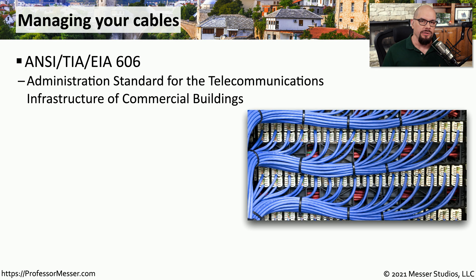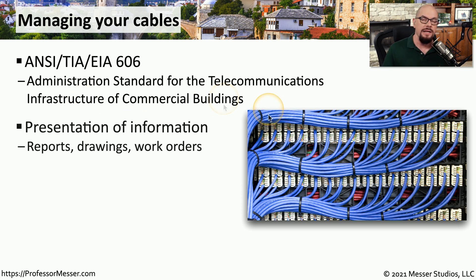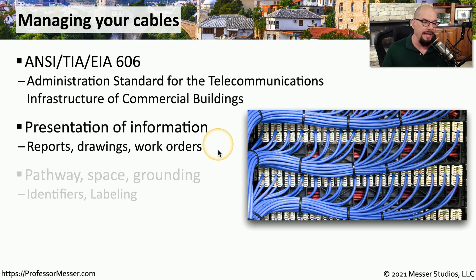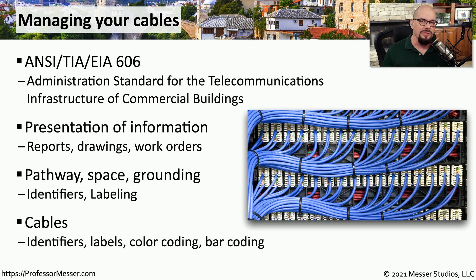As network professionals, not only are we documenting our switches and our routers, but we're also documenting all of the cables in our organization. Fortunately, there is a standard for documentation: the ANSI TIA EIA 606. It's the administration standard for the telecommunications infrastructure of commercial buildings. This can help you with best practices for creating reports, drawings, or work orders based on this cabling. You can also get an idea of how to document the pathways, the space, the grounding, and how to label all of these cables in your organization.